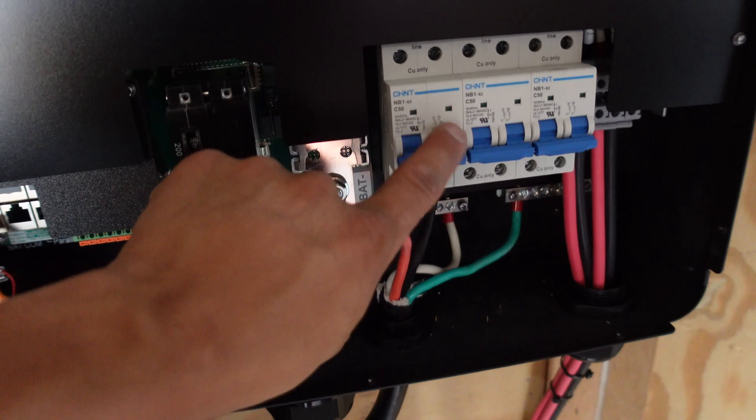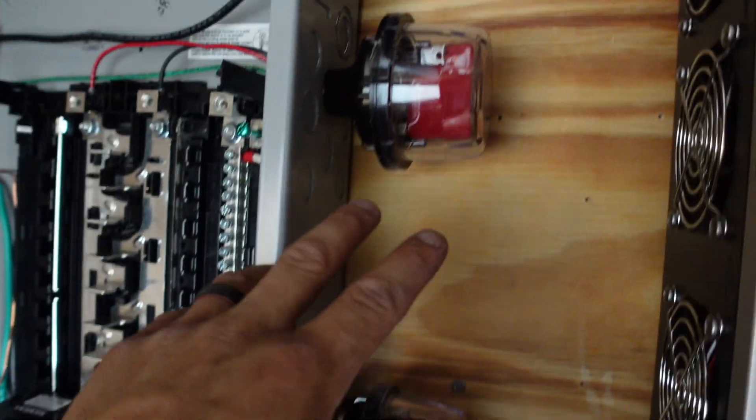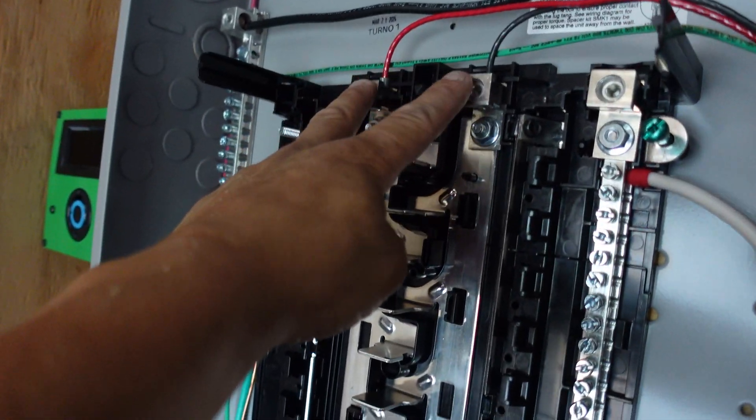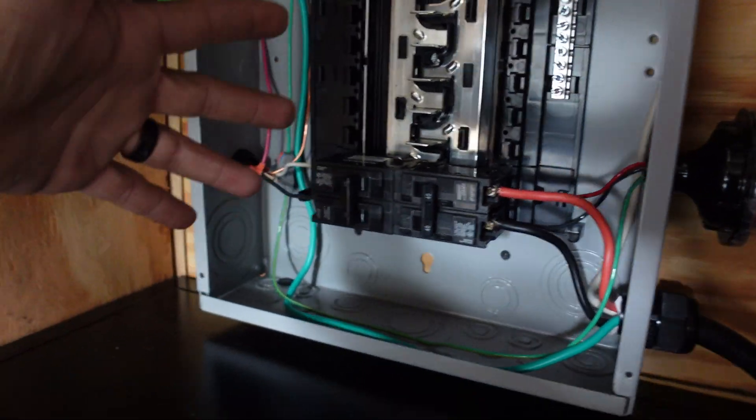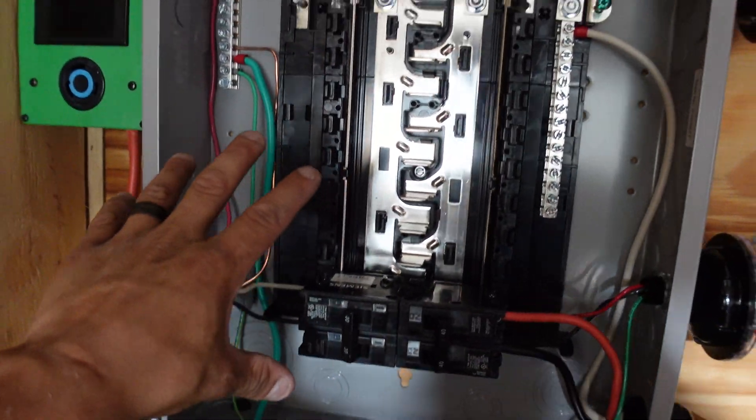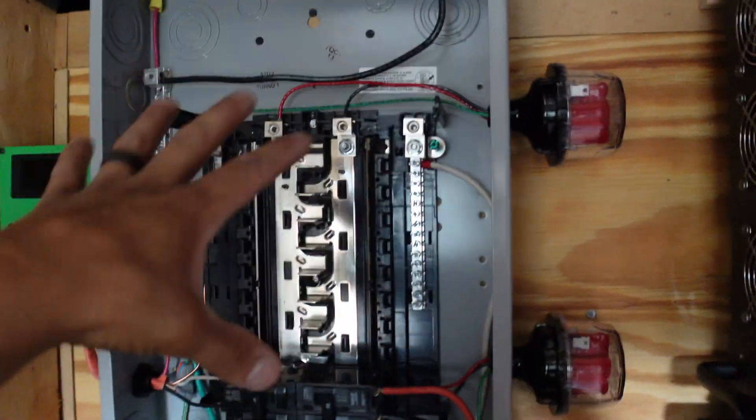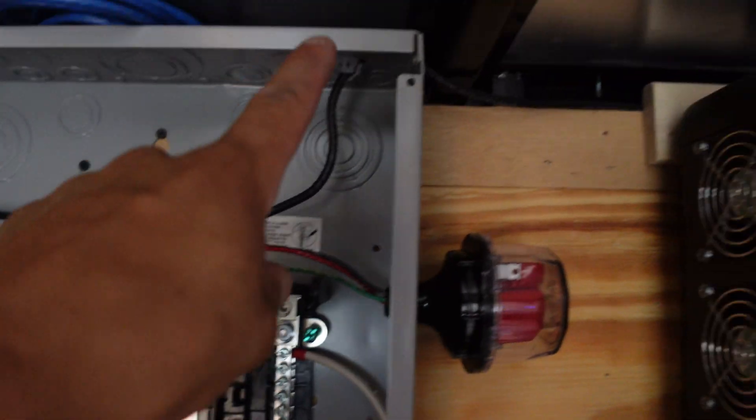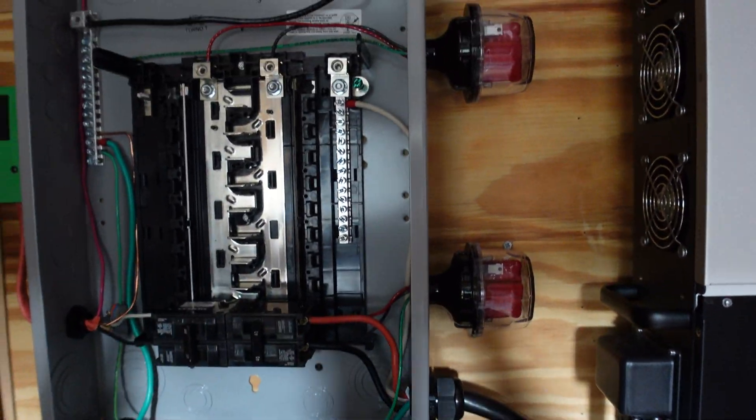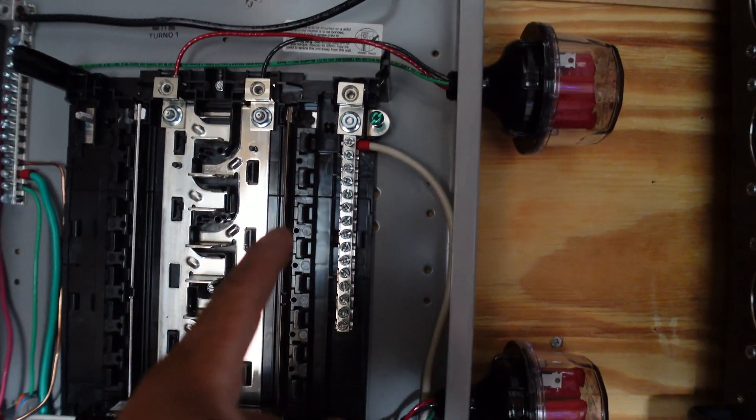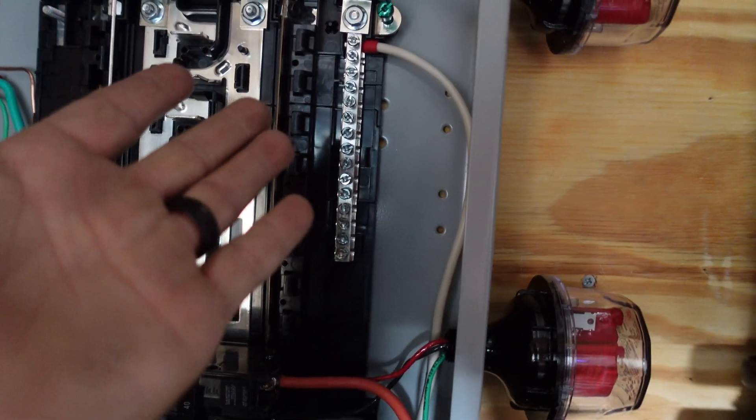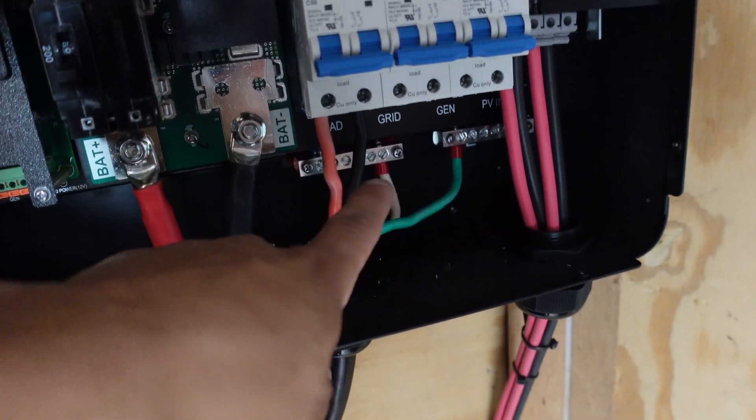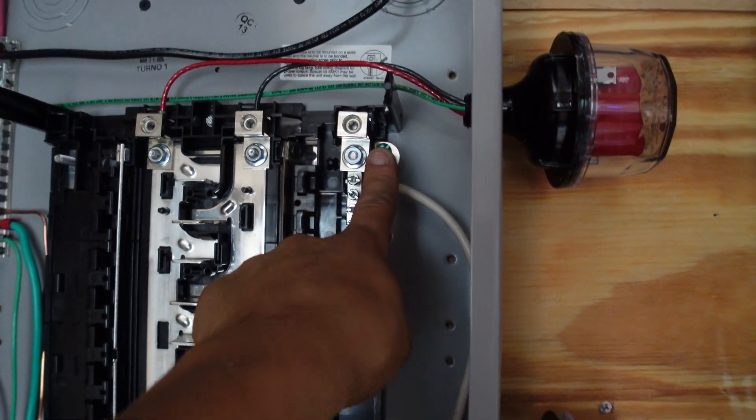Anyways, you can see I got the 40 amp here with the two positives, they're both 120 volts feeding both these legs. I have a surge protector going directly into this 40 amp, so this inverter is covered if this breaker's off for whatever reason and this one is still on. And then I also added another surge protector that is going for the entire two legs on the panel to obviously protect anything going on the outside. If I added that 20 amp breaker, that would be covered by this surge protector as well. Then I got all the grounds over here tied together. Got the ground wire actually going outside, I actually zip tied it along this guy right here all the way down through to the ground rod that I pounded in eight feet.